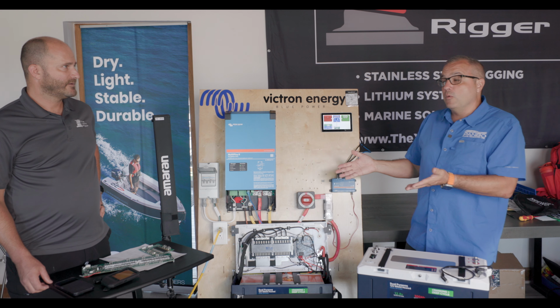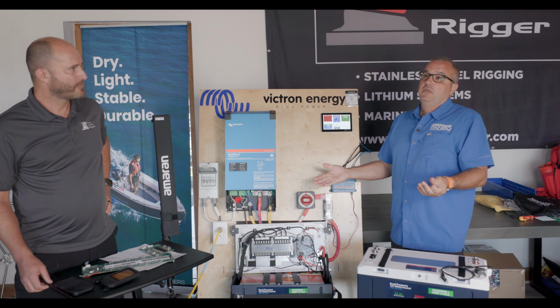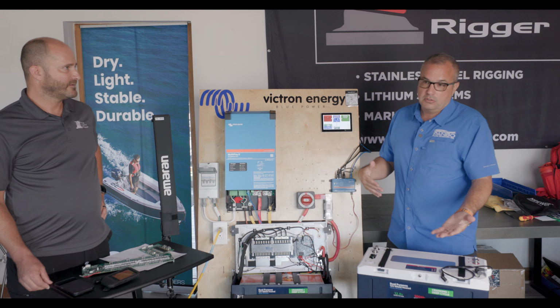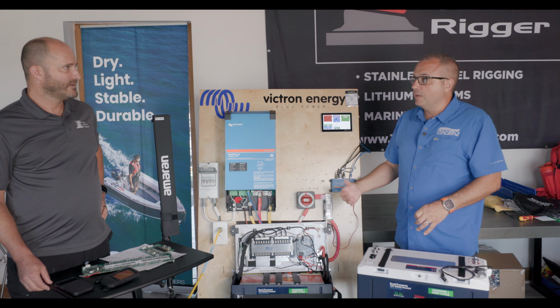I think historically that's been one of the challenges. Often you've got to have a separate battery for the windlass or some scheme to mitigate that load. Specifically the bow thrusters draw so much load that a lot of the BMSs will cut out. They don't like that inrush current, but I think this will handle that with no issues whatsoever.